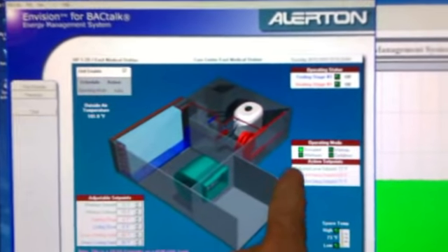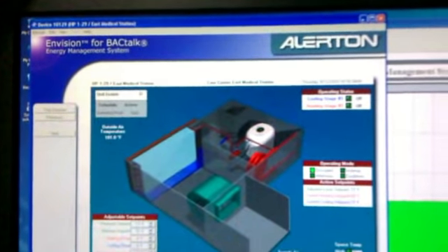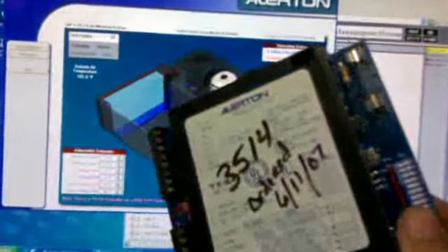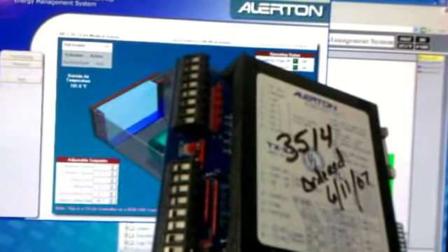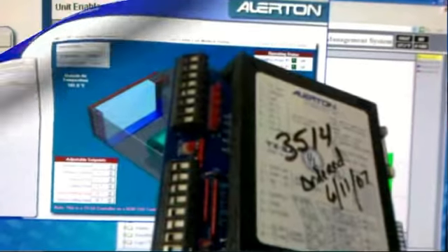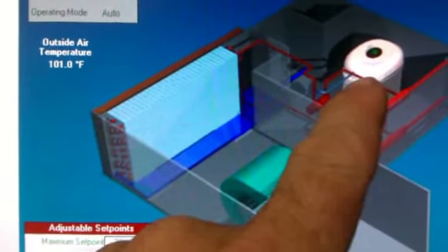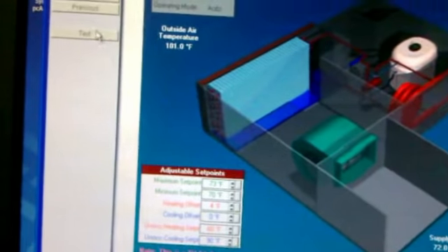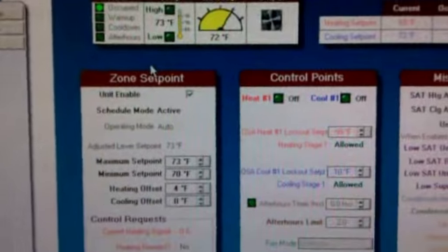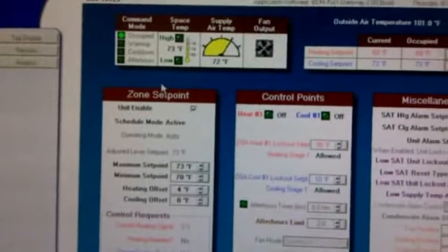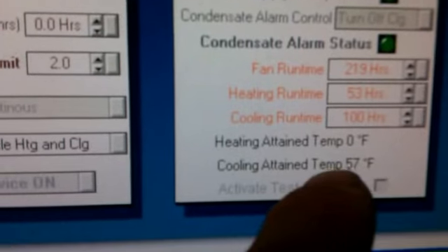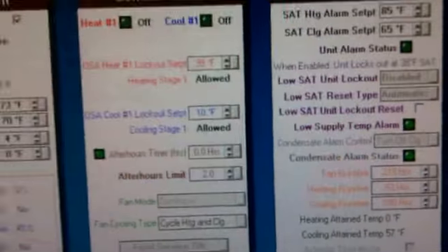And these are using the Alerton boards. Oops, they look like this. You set the addresses, and it's just got the digital input outputs. Compressor's not running right now at the set points. Usually we'll view this in text mode. It's a little easier to see everything. Fan's still running, compressor's not. Supply temp achieved 57, so it's doing good. Nothing's in alarm.